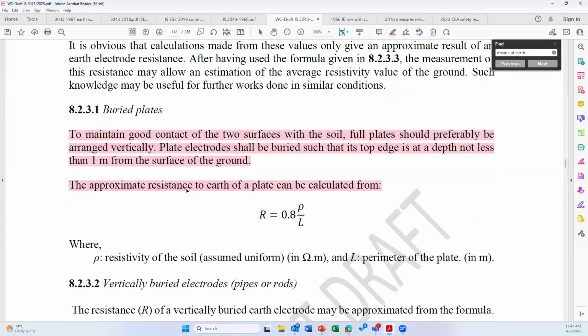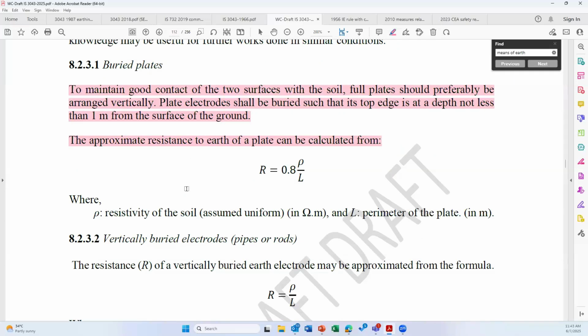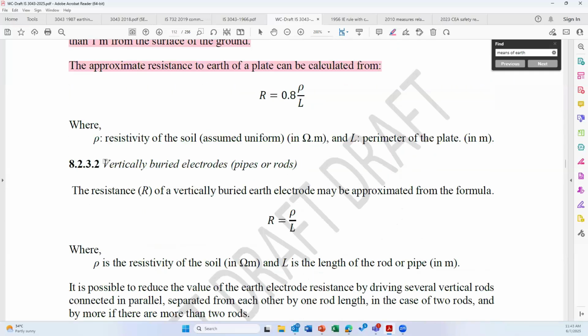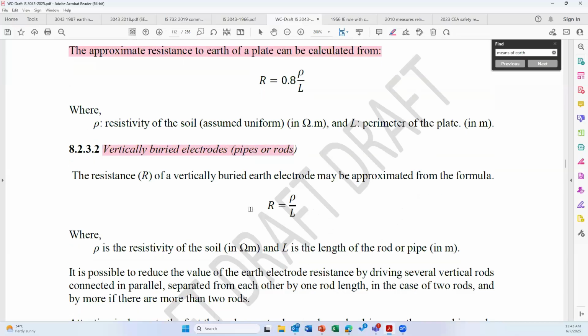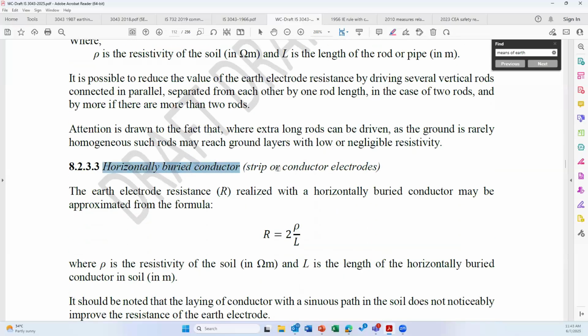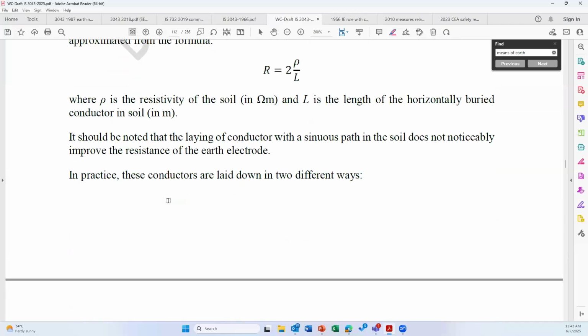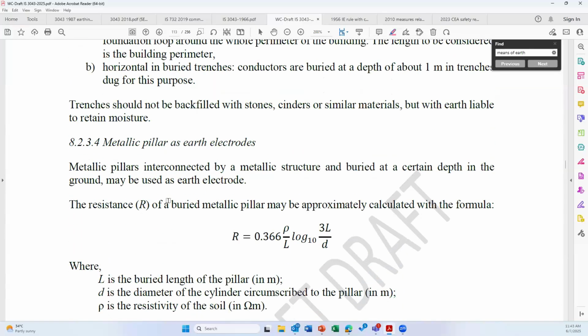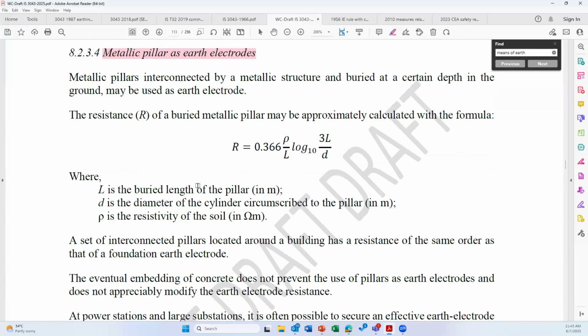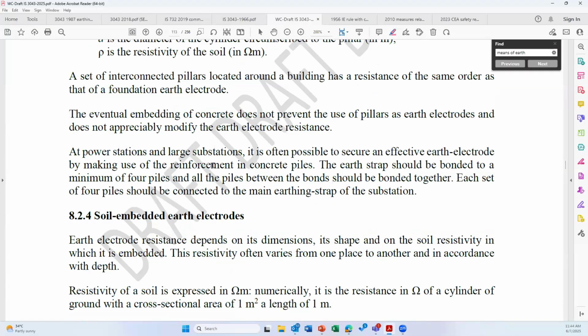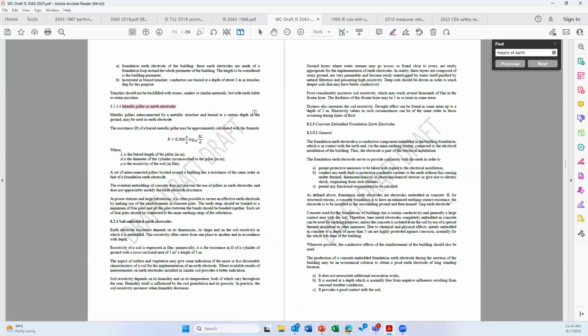You can see here, in case of a buried plate, how to calculate the earth electrode resistance. In case of a vertically buried electrode rod, how to calculate the earth electrode resistance. In case of a horizontally buried conductor, how to calculate the earth electrode resistance. And metallic pillars as earth electrode, how to calculate. So basically, please note that I will not say these are new calculations. These are improved calculations or simplified calculations.